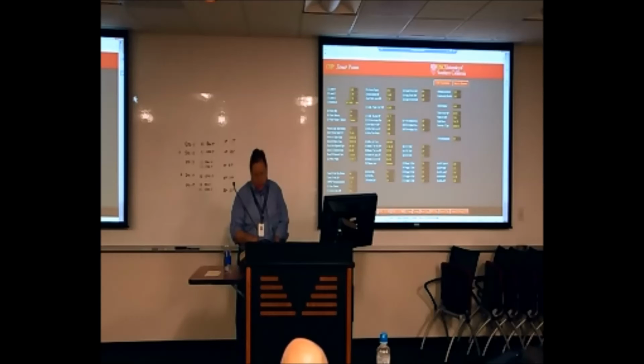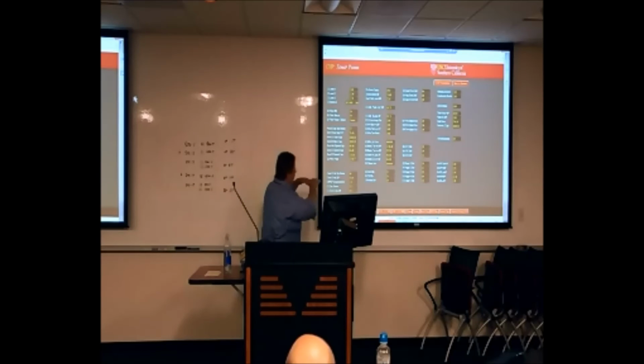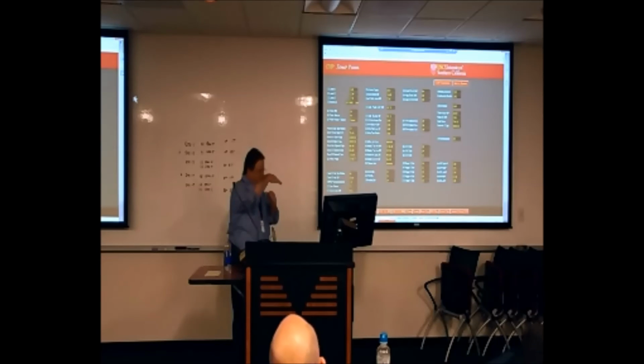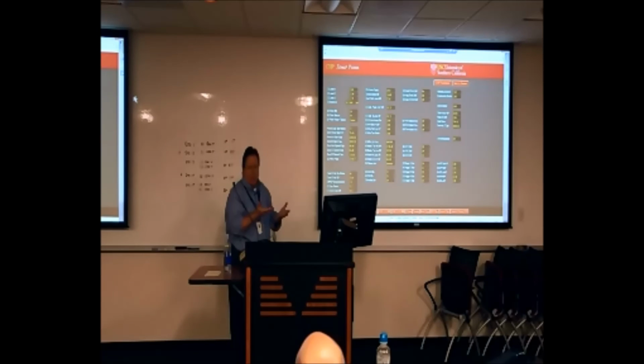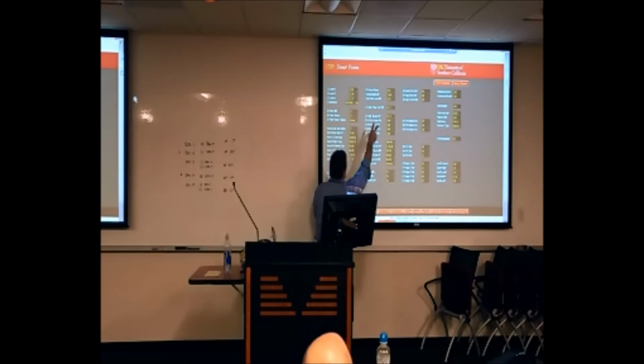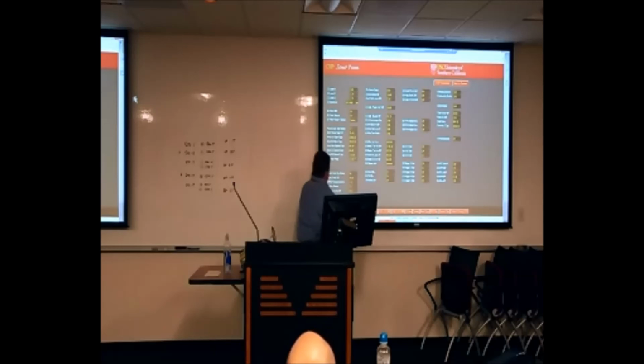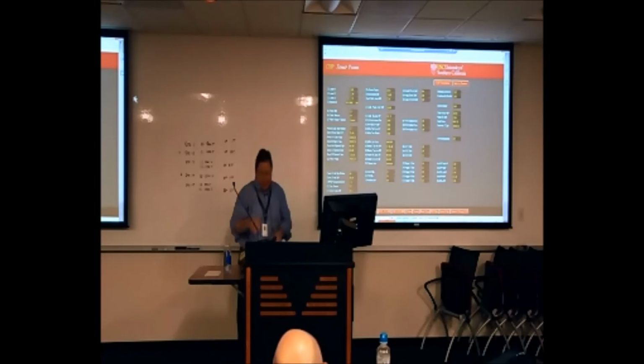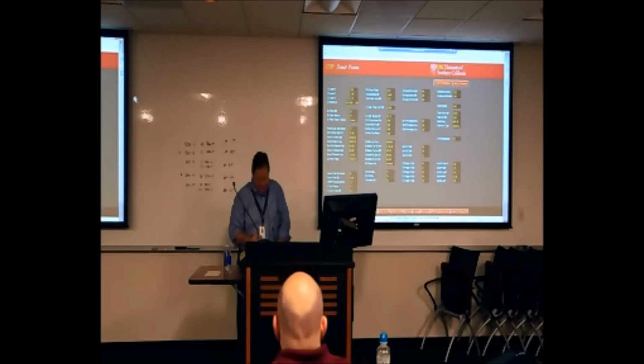Another criteria is we're looking at the wet bulb plus 7. The next one up, I should say, would be wet bulb plus 7. So we'll take our wet bulb temperature, add 7 to that, and that's as low as it's going to drive that temperature down to. The advantage there is if we had a wet bulb such that we weren't able to get a really cold condenser water temperature, then we're not going to try to get there. We're not going to waste the energy trying to get there. It's going to float that temperature up a little bit, so we're not wasting energy trying to get to that low condenser water supply temperature. So it's attempting to get to that chill water plus 15, but it might float up a little bit based on the wet bulb temperature plus 7.